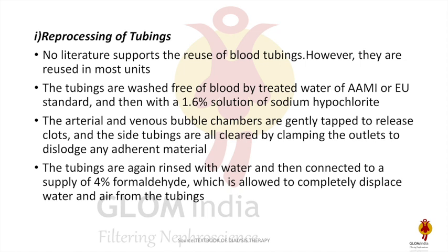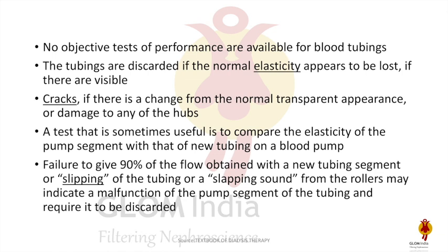Regarding reprocessing of tubing: there is no literature available for reuse of blood tubing, however it is reused in most units. The tubing is rinsed free of blood with water, then with 1.6% sodium hypochlorite. The arterial and venous bubble chambers are gently tapped to release clots, and the side tubings are cleaned by clamping the outlet to dislodge any adherent material. The tubings are again rinsed with water, then connected to a supply of 4% formaldehyde. There are no objective performance tests for blood tubing; loss of elasticity, cracks, or a squeaking sound from the tubing are indicators that it is not in a proper state to be used.